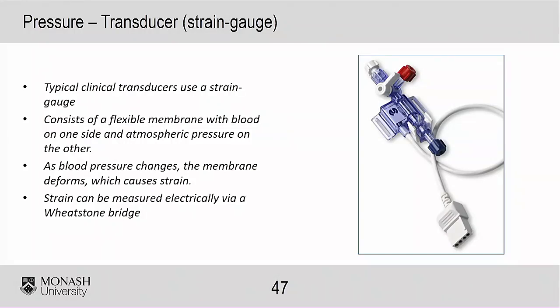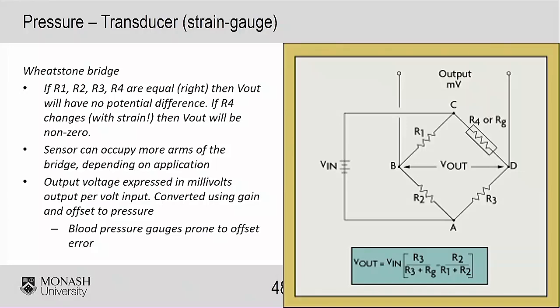As the blood pressure changes, the membrane in that sensor deforms. So you have a deformable component here, a mechanical component, and that causes strain, which we're going to look at on the next slide. And strain, essentially the deformation of that flexible membrane, can then be measured electrically using a Wheatstone bridge. So for the electrical engineers in the room, you can probably explain this much better than I can, but for everyone else, it's a fairly simple circuit. If you have an inlet voltage coming in here, and you're measuring the voltage between B and D, if all of these resistances are the same, then there's not going to be any voltage difference between these 2 points. If one of them changes, in this case R4, then there will be a voltage change between those 2 points, and you can calculate it using this.